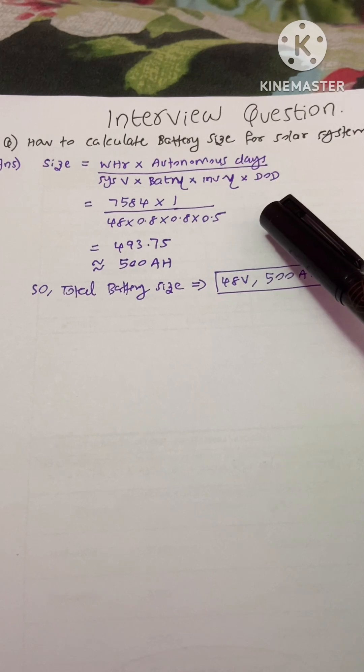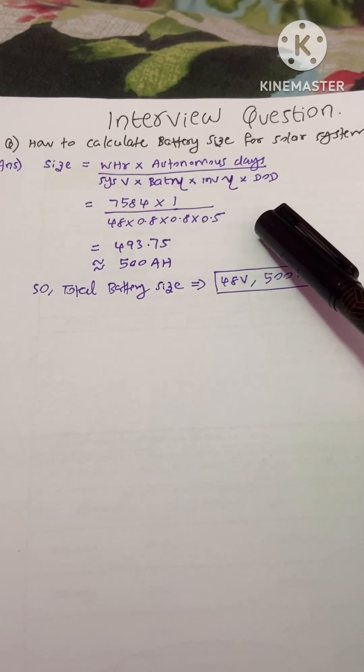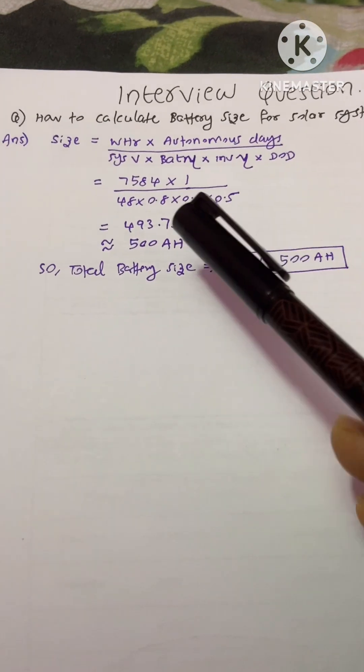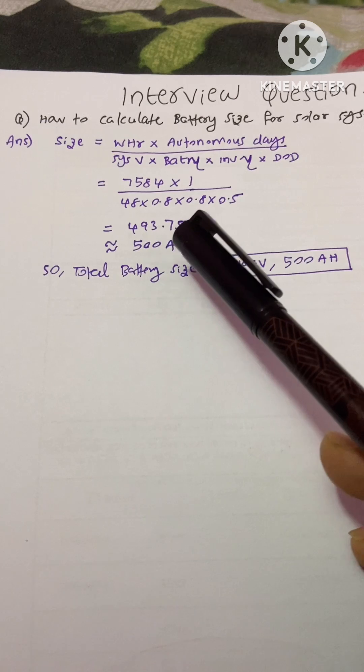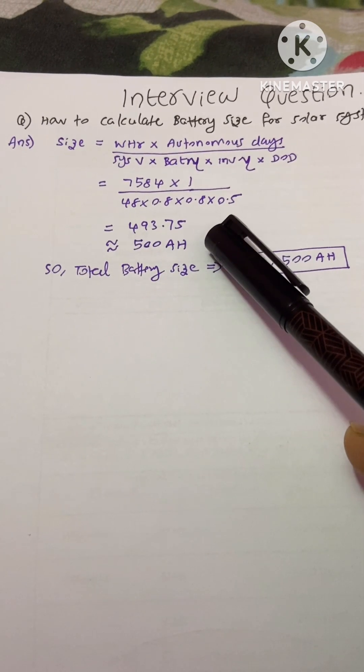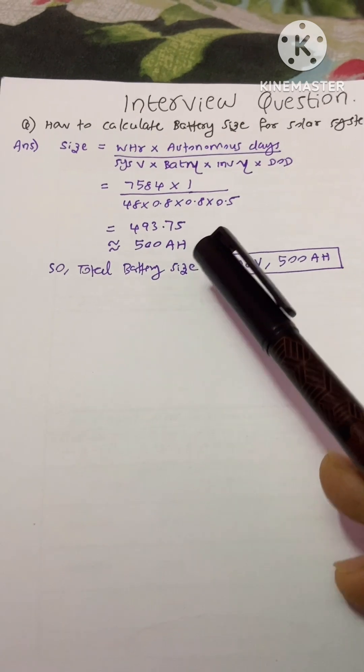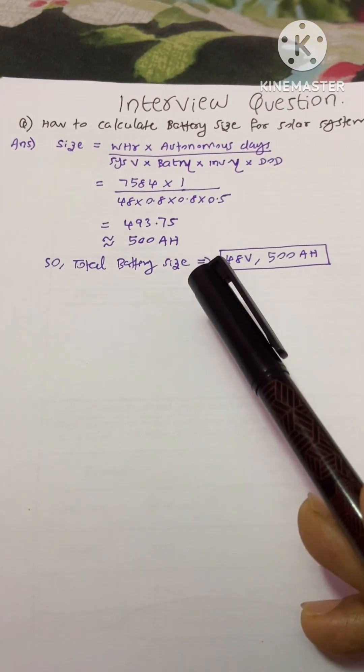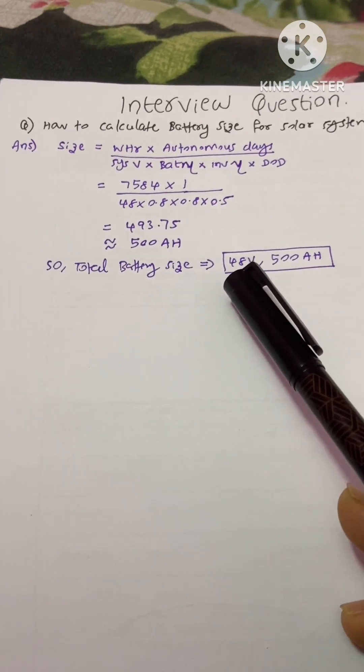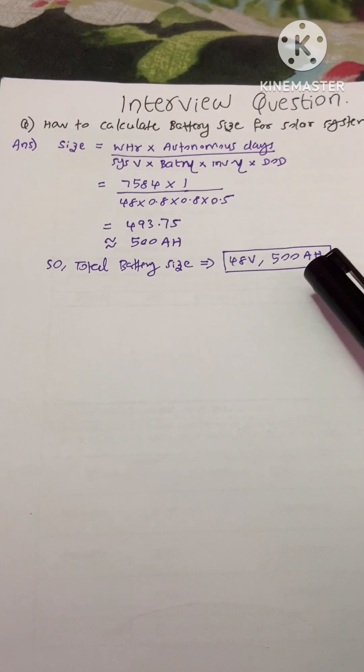If you take more DOD then your battery life will be lesser. We got the answer 493.75 Ah, approximately 500 Ah ampere hour. So the total battery size is 48 volt 500 Ah.